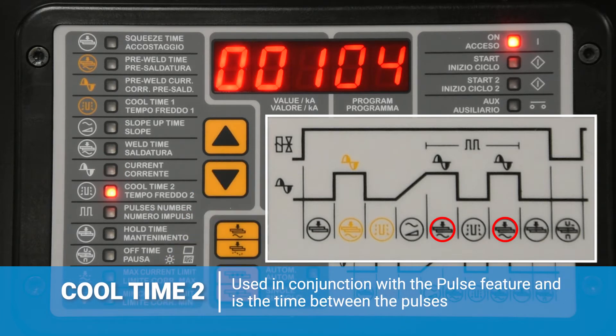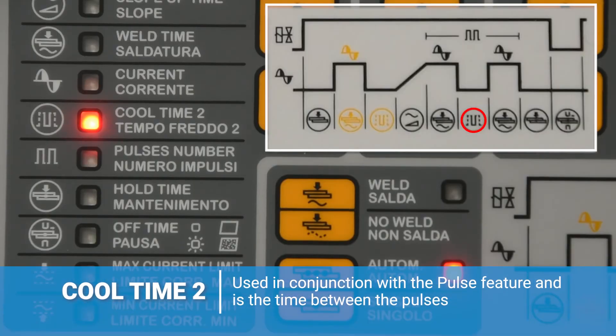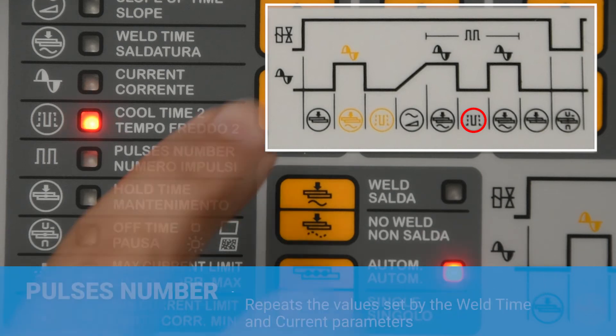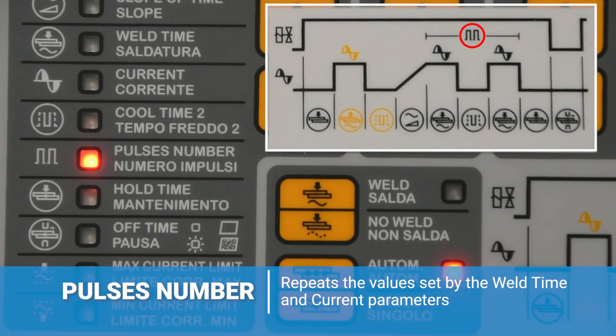Next, we have cool time 2, or the second cool time, and this is used in conjunction with the pulse feature. This is the time between pulses and can be set between 1 and 50 cycles. The next parameter is pulses number, or number of pulses. The TE101 can be set between 0 and 9 pulses. When set to 0, no pulsing will occur.